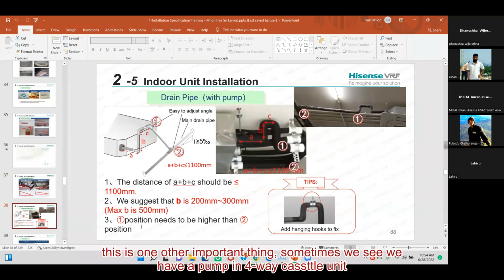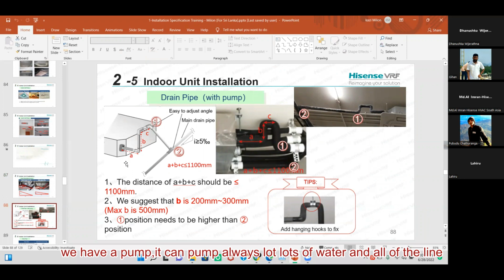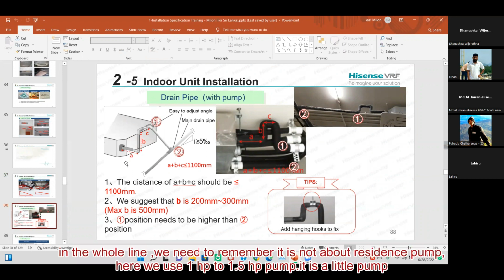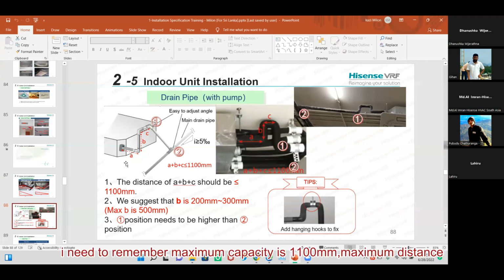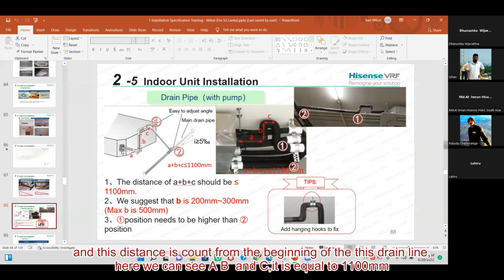This is another important thing. Sometimes we have a pump in a cassette type unit, and we feel it can pump lots of water through the whole line. We need to remember it is not a residence pump. Here we use a 1 HP or 1.5 HP pump. It is a little pump. Its maximum distance capacity is 1100 millimeters, and this distance is counted from the beginning of the drain line.